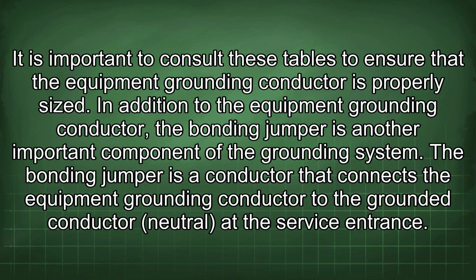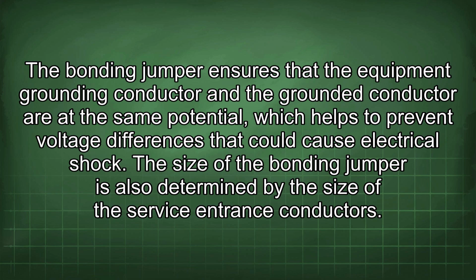In addition to the equipment grounding conductor, the bonding jumper is another important component of the grounding system. The bonding jumper is a conductor that connects the equipment grounding conductor to the grounded conductor (neutral) at the service entrance. The bonding jumper ensures that the equipment grounding conductor and the grounded conductor are at the same potential, which helps to prevent voltage differences that could cause electrical shock.